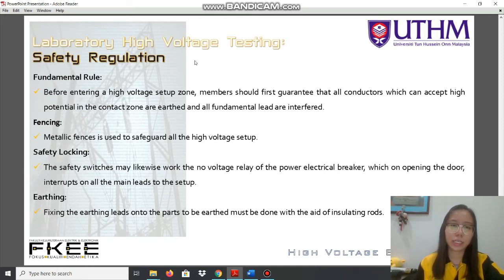I'm going to present the high voltage testing part. The safety regulation is very important, and we need to know this safety regulation before we conduct the high voltage testing. First, for the fundamental rule, before entering a high voltage room setup, all the members should first guarantee that all the conductors or the equipment which can accept the high potential in the contact zone are earthed and all the fundamental leads are interfaced. This is to ensure that the voltage or the current that lives in the equipment is discharged.